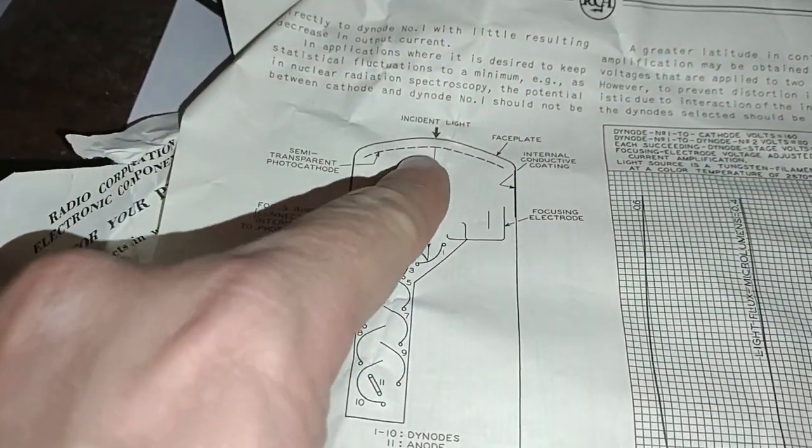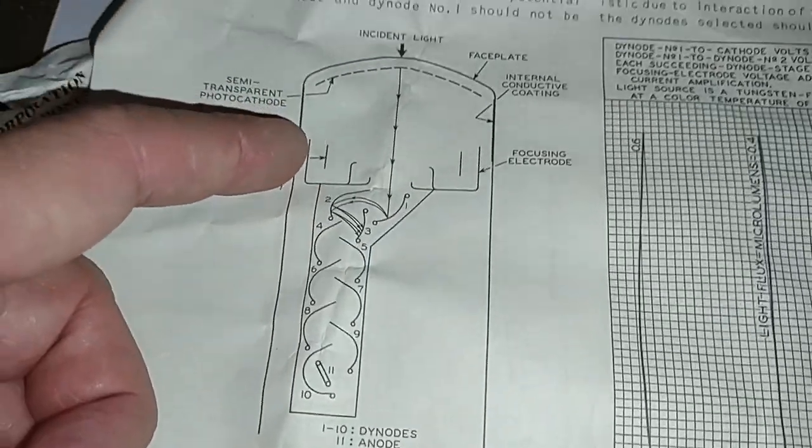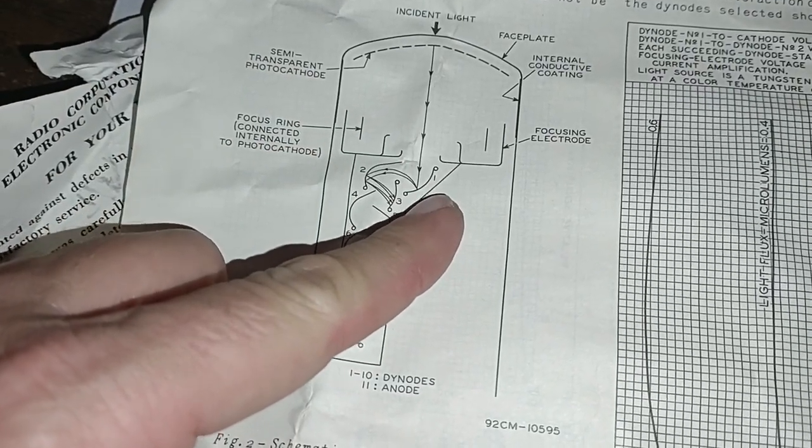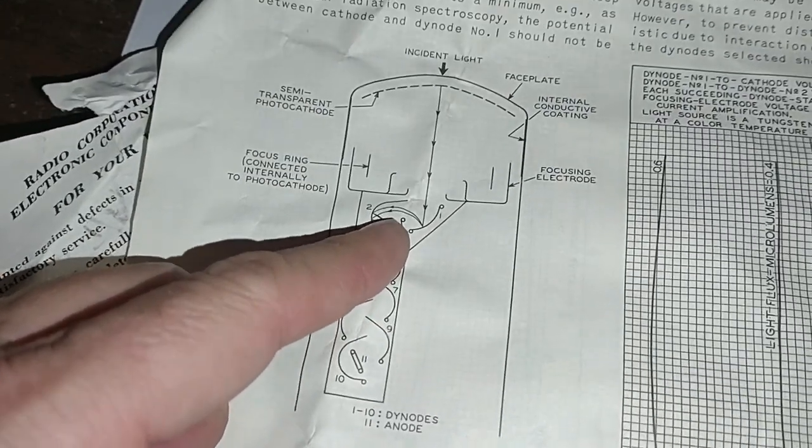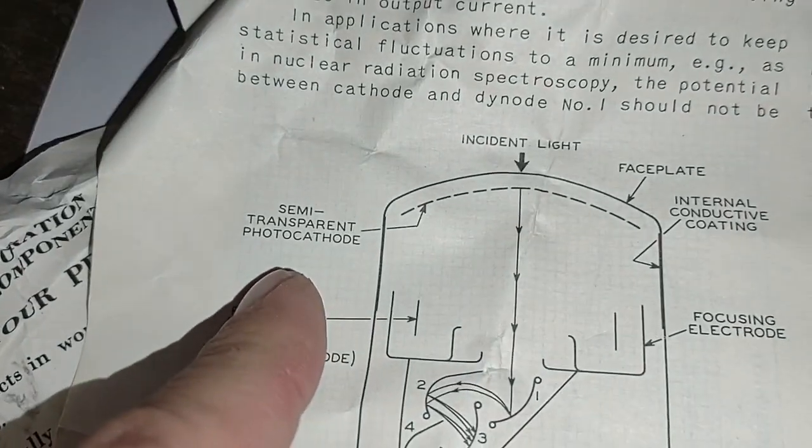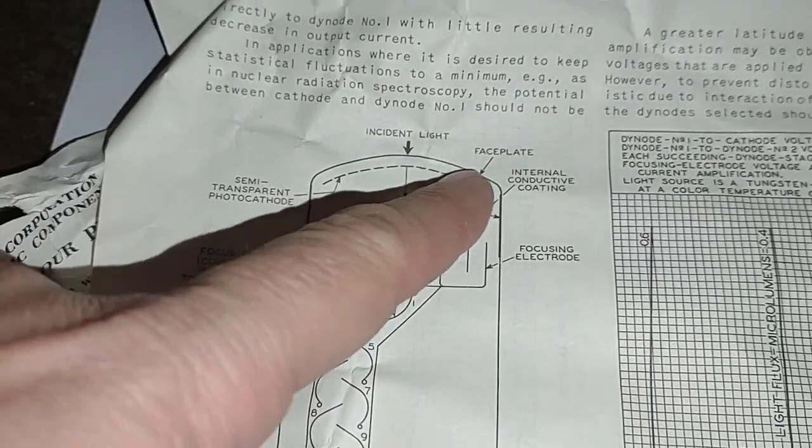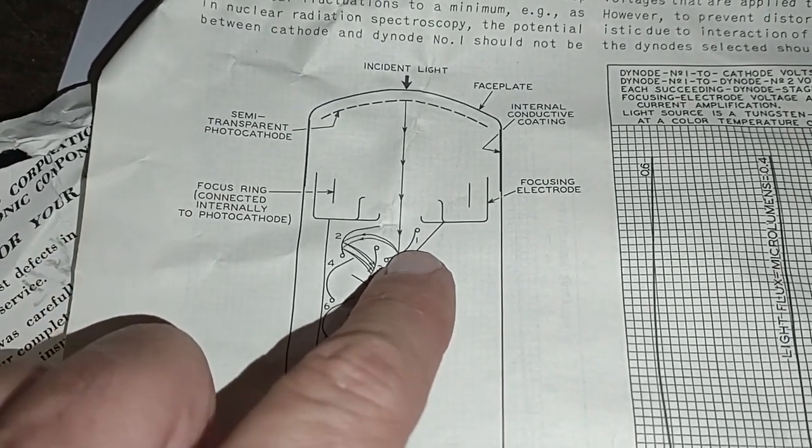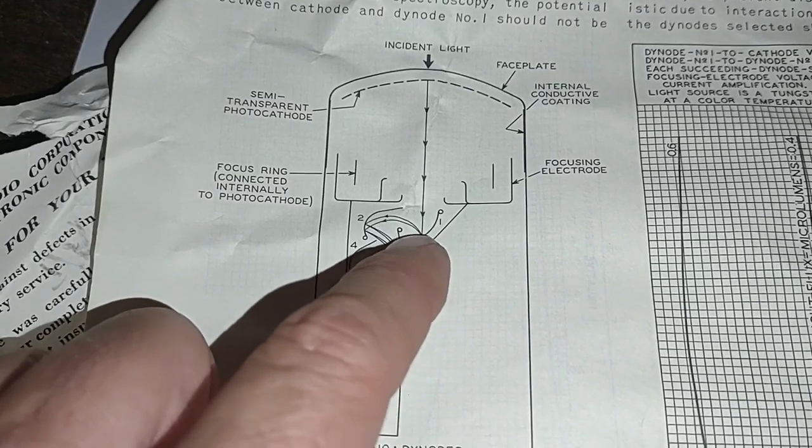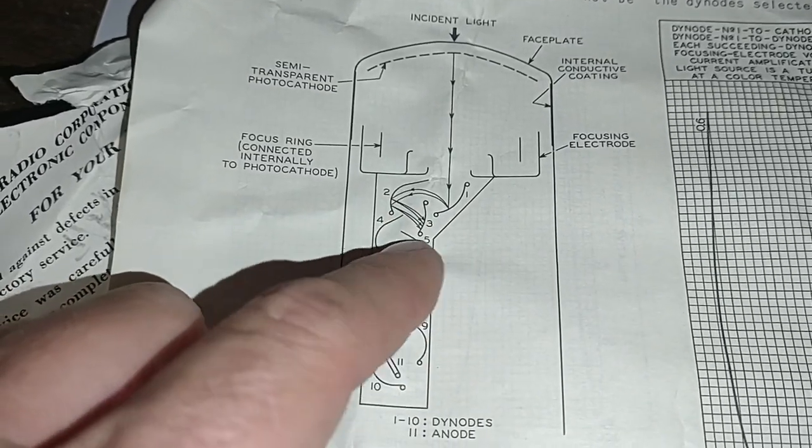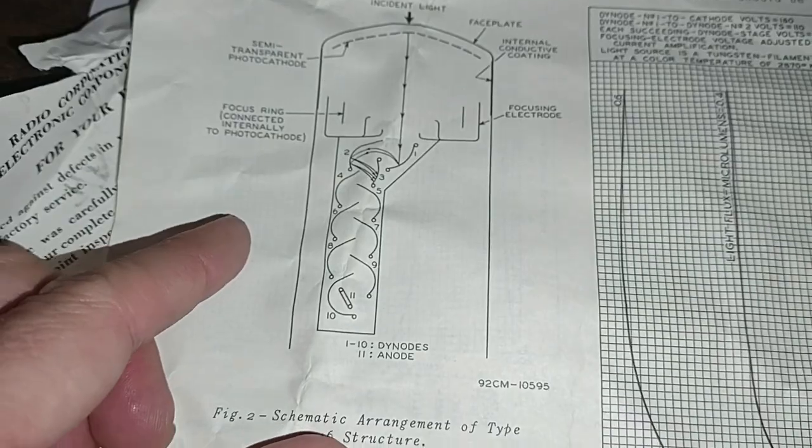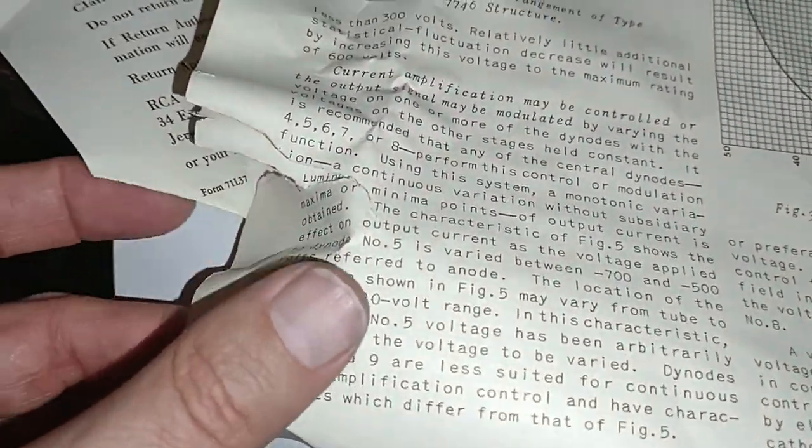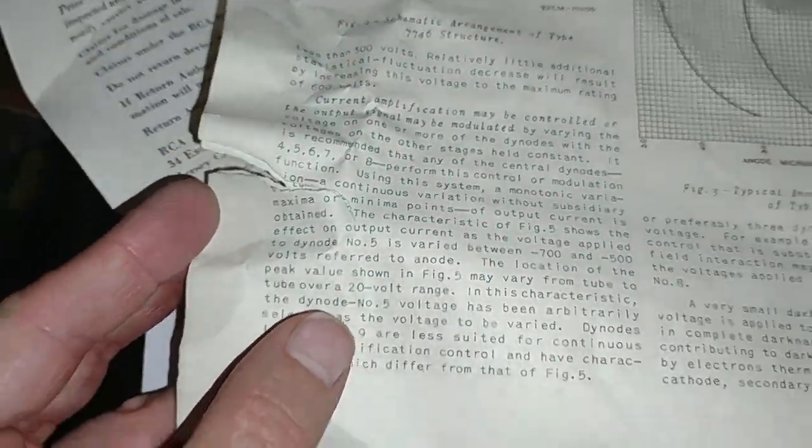The light comes in through here and then it'll knock off an electron on the photocathode. The photocathode is up here, so it knocks an electron off when a photon comes in, then it hits the first dynode and the current's amplified. Second dynode, third, fourth, on down the chain. Very cool. So there's the theory of how this guy works.